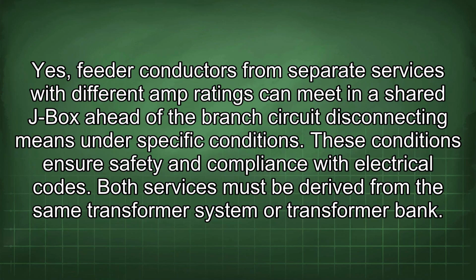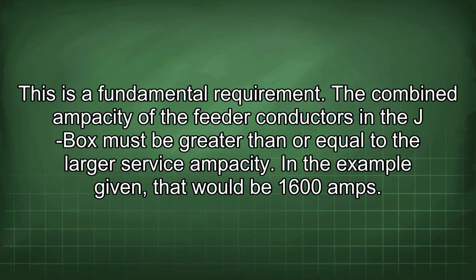Yes, feeder conductors from separate services with different amp ratings can meet in a shared J-box ahead of the branch circuit disconnecting means under specific conditions. These conditions ensure safety and compliance with electrical codes. Both services must be derived from the same transformer system or transformer bank. This is a fundamental requirement.